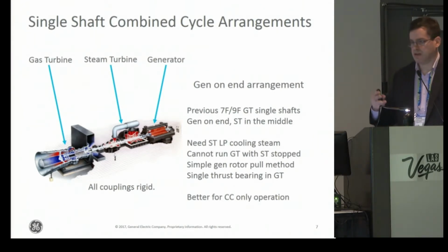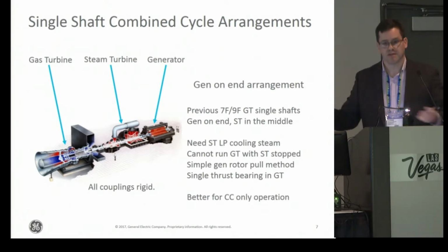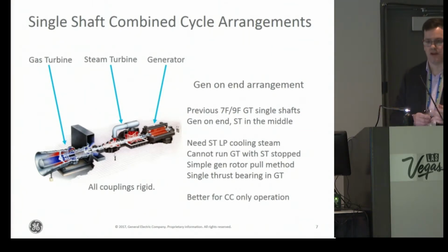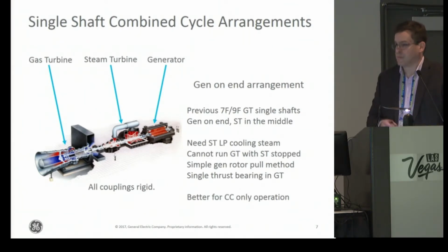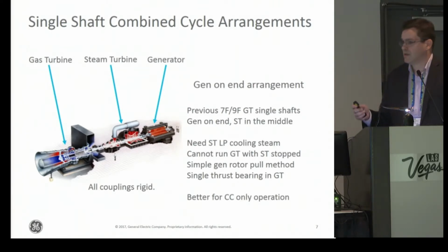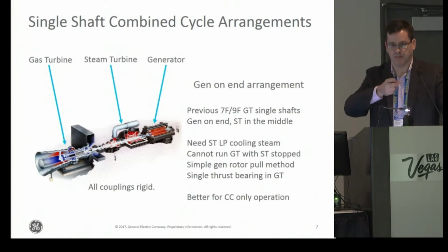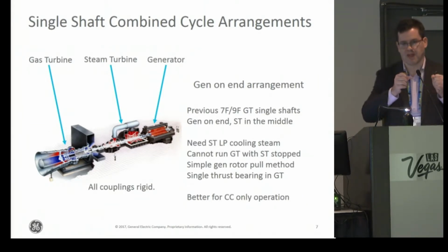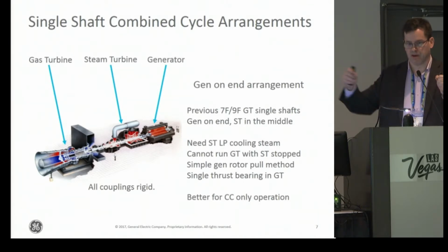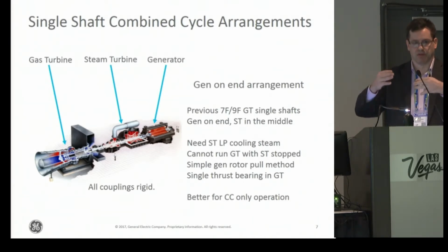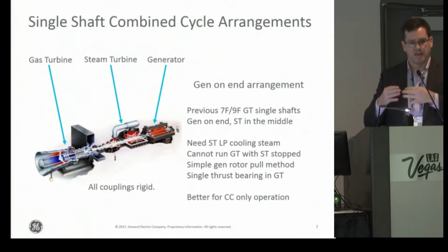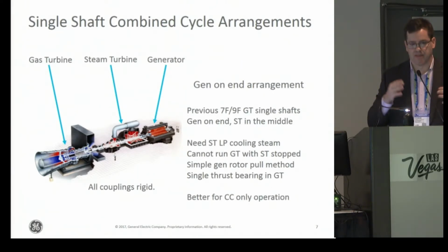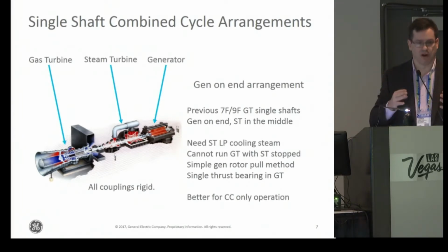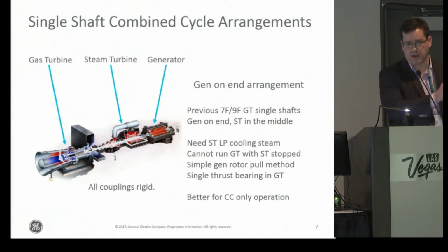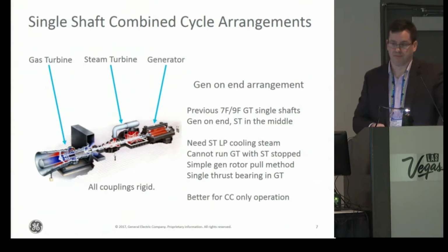However, it does drive some problems as well. If you have an indoor arrangement, then you have to have room inside the building to take that field out, so it potentially makes for a larger installation. Also, with regard to efficiency, since your thrust bearing is in the gas turbine, and you have axial expansion from that thrust bearing all the way back to the generator through the steam turbine rotor, you're going to have to leave some pretty big axial clearances when you're cold to make sure you have good clearances when you're hot. And those clearances, say at part load, are going to impact your efficiency, because you have so much expansion from that thrust bearing, since you have only that one thrust bearing.